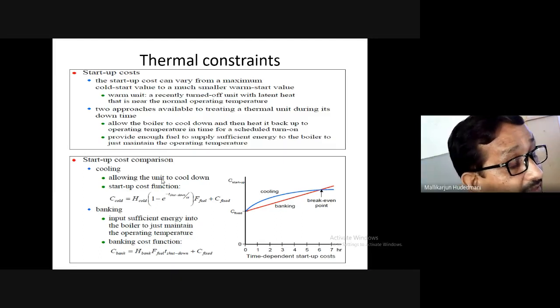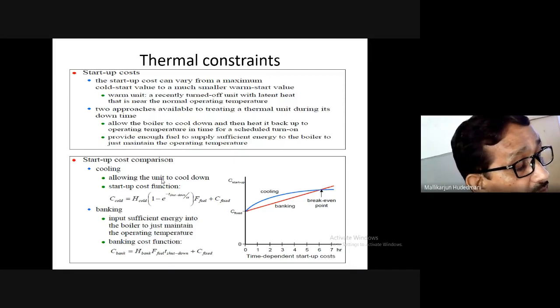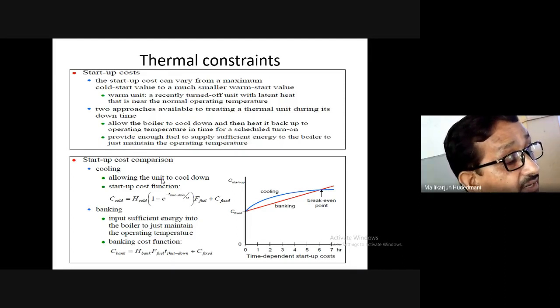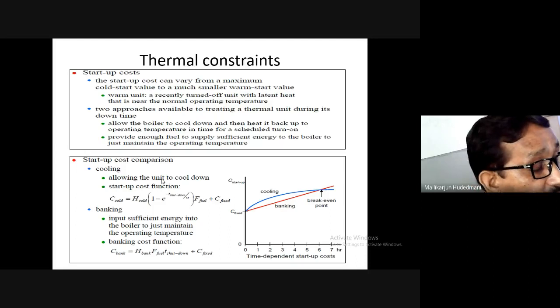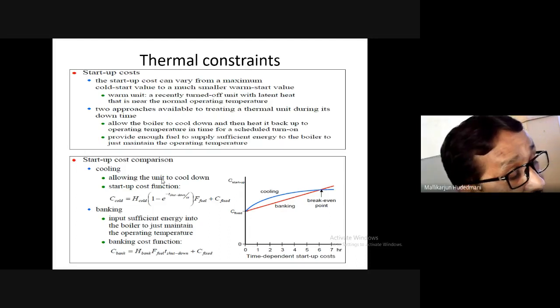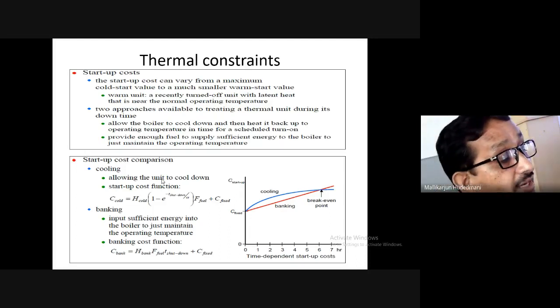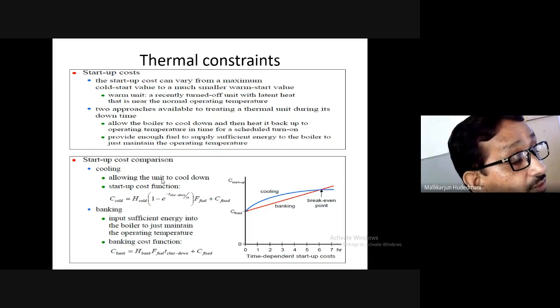Rather than cooling it to room temperature, maintain it by burning reduced fuel, keeping it at a certain lesser temperature so that it keeps spinning. It runs on the minimum possible fuel so that when fuel is increased, it is ready to come online in a shorter duration.